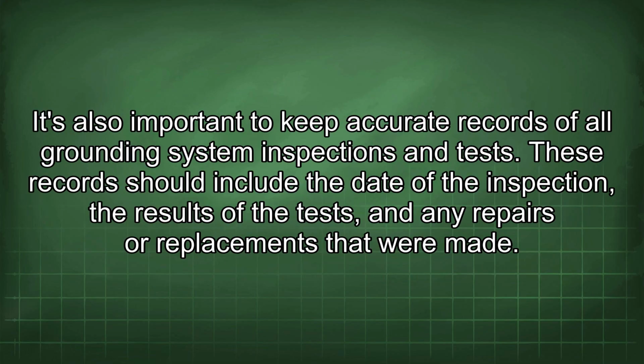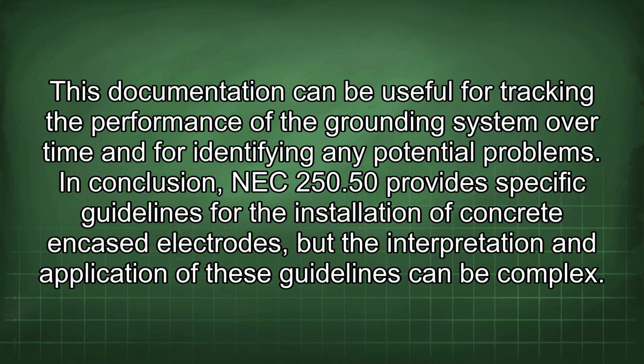It's also important to keep accurate records of all grounding system inspections and tests. These records should include the date of the inspection, the results of the tests, and any repairs or replacements that were made. This documentation can be useful for tracking the performance of the grounding system over time and for identifying any potential problems. In conclusion, NEC 250.50 provides specific guidelines for the installation of concrete encased electrodes, but the interpretation and application of these guidelines can be complex.